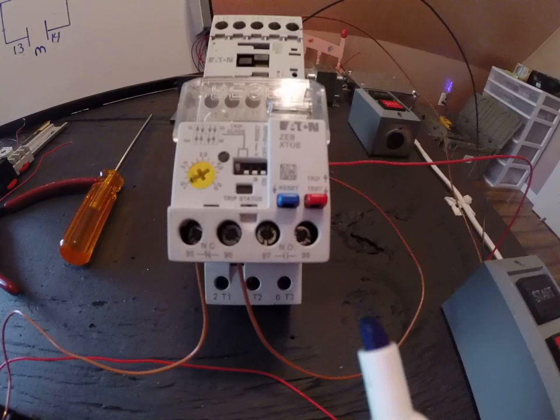Now if this motor trips on overload, what's going to happen is these two little buttons right here... watch, I close this cover, part of this button is actually hitting reset, and I could test it by pulling out the knob.